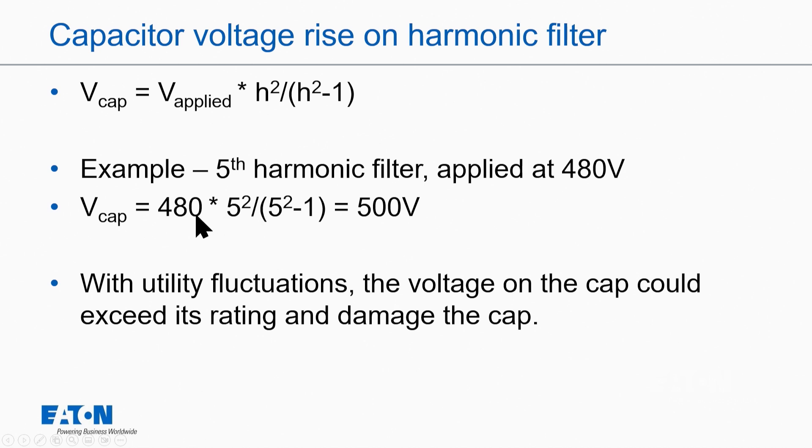So for example, for a fifth harmonic filter, you'd have 480, which is the applied voltage, times five squared over five squared minus one, which gives you about 500 volts.